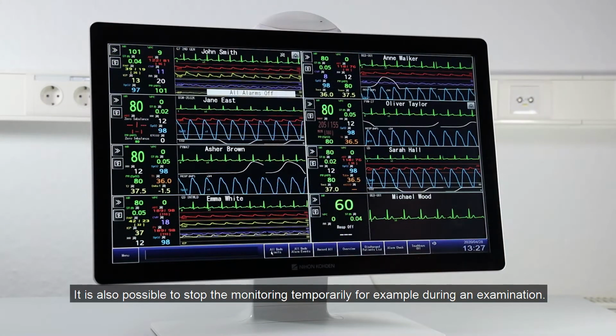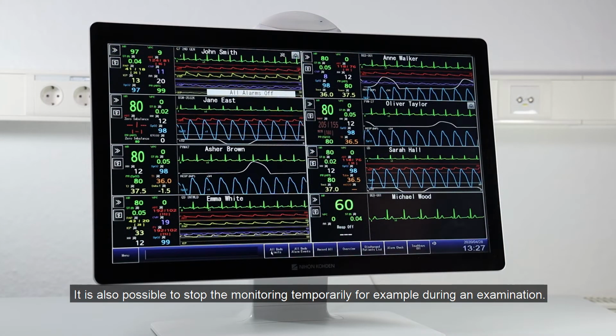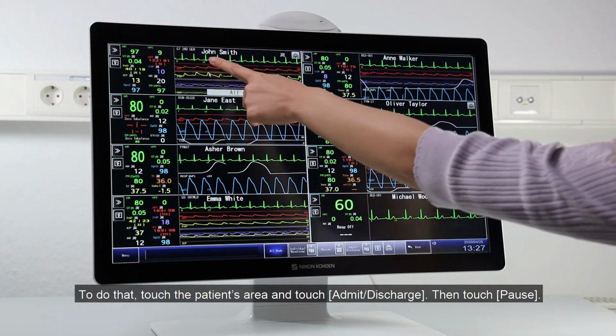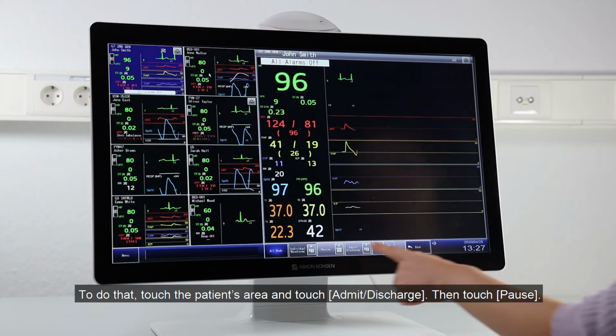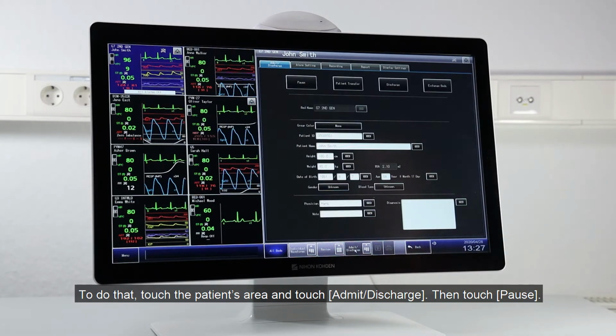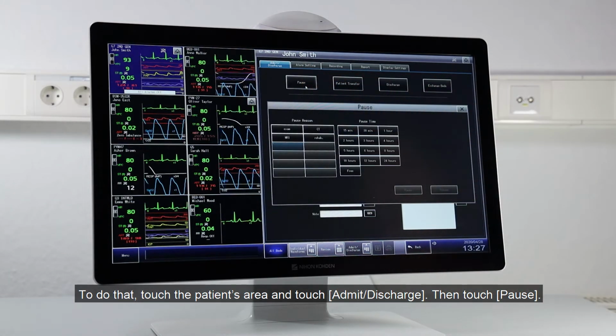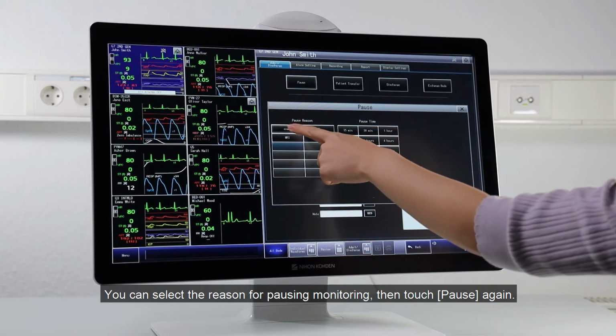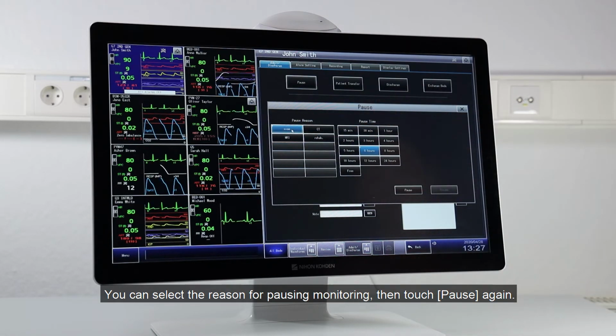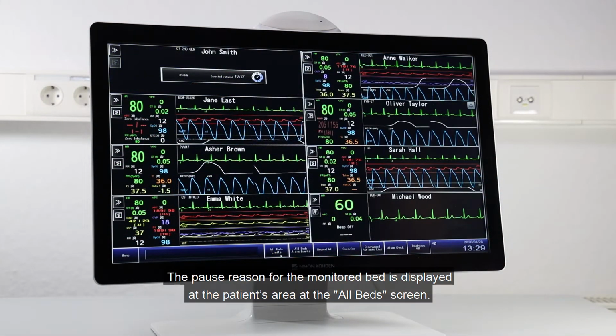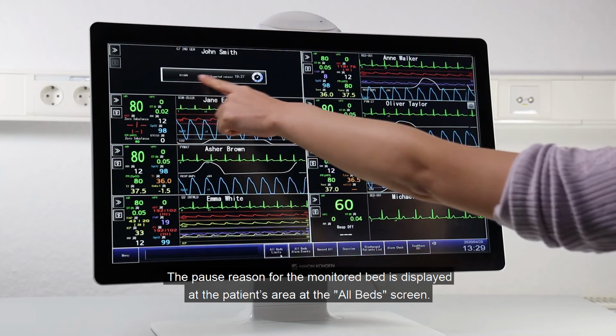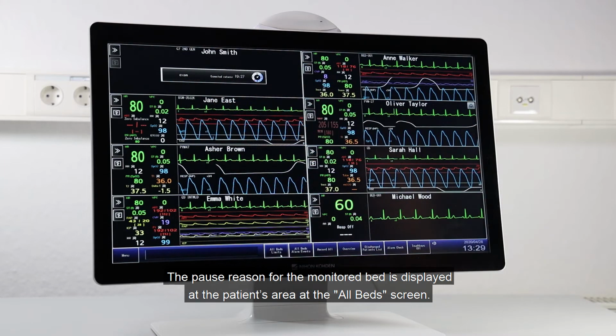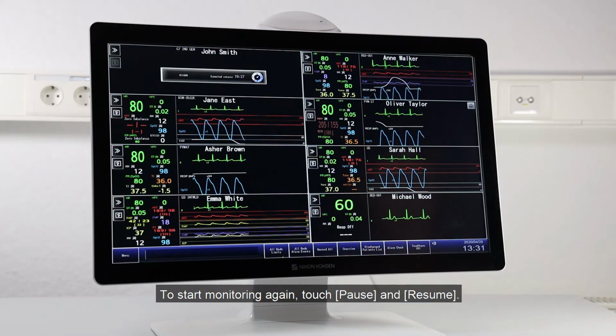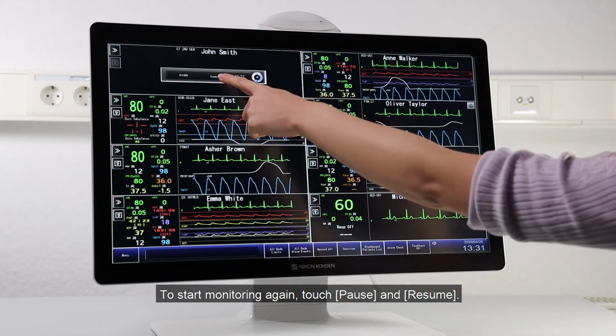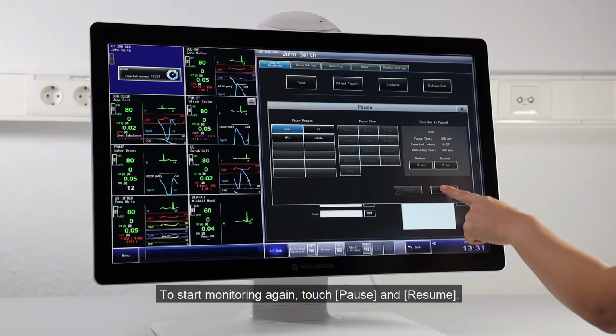It is also possible to stop monitoring temporarily, for example during an examination. To do that, touch the patient's area and touch Admit Discharge. Then touch Pause. You can select the reason for pausing monitoring, and then touch Pause again. The pause reason for the monitored bed is displayed at the patient's area at the All Beds screen. To start monitoring again, touch Pause and Resume.